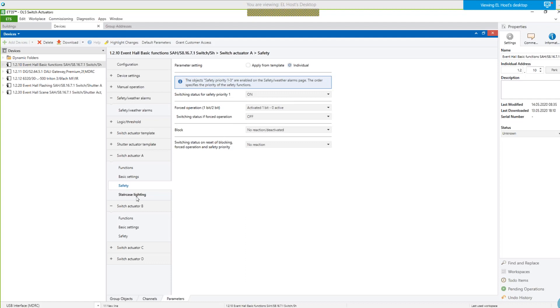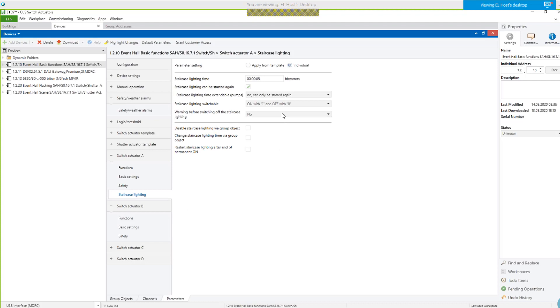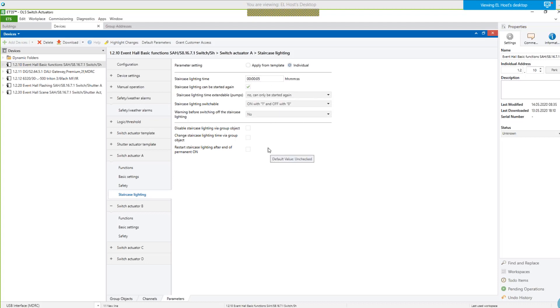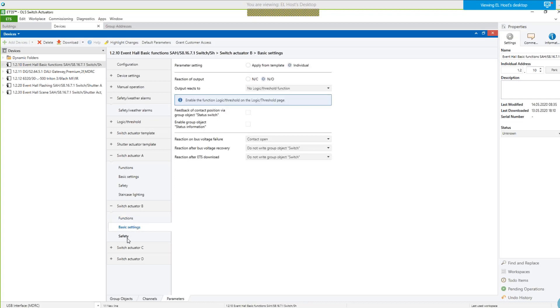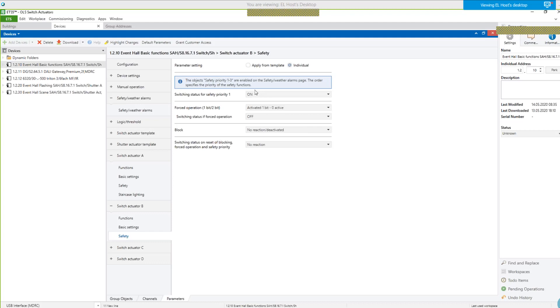Then I need the staircase lighting for the entrance area. I have parameterized only five seconds here for testing. It's a standard staircase lighting — no additional features like re-triggering or pump-up staircase time. Switch actuator B also needs the priority switching because it's involved in case of fire alarm and for central switch off, but no staircase time function needed. Under safety, it's the same as the entrance area: on for fire alarm, off for the central off function.